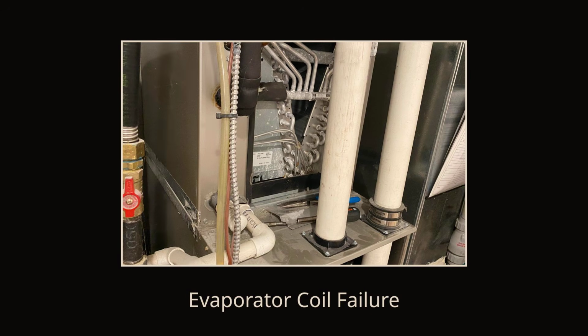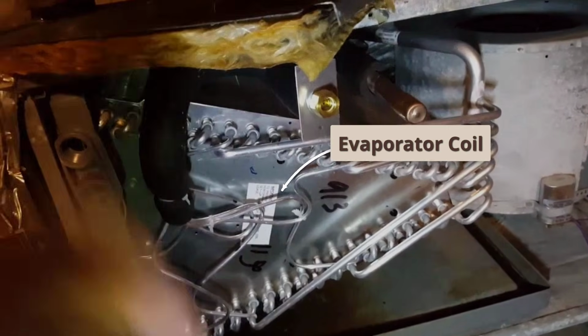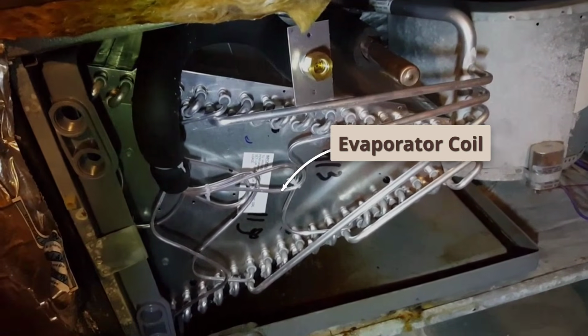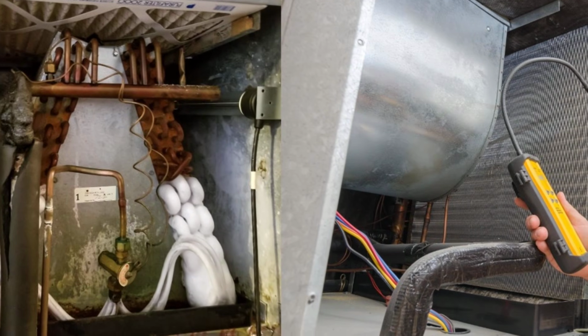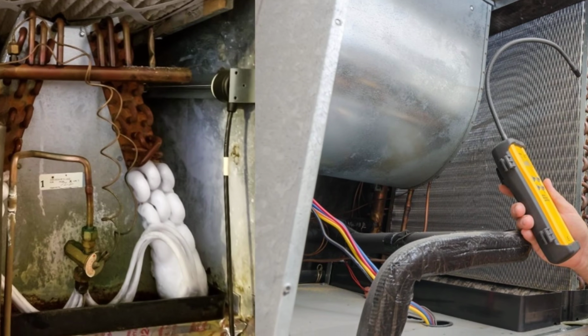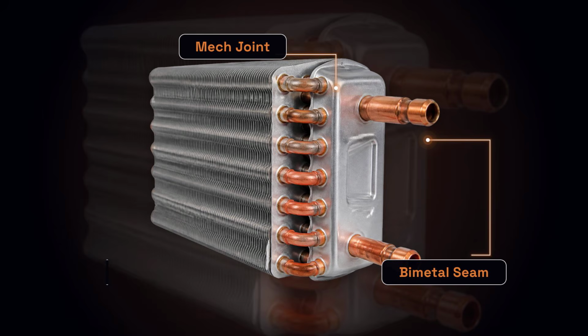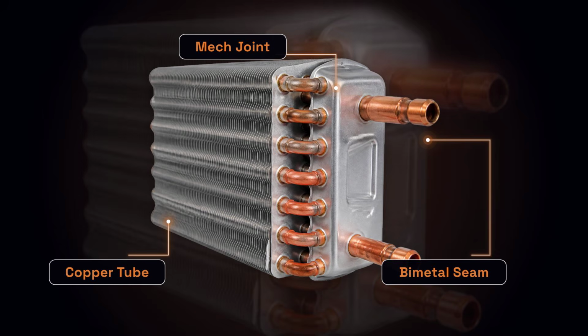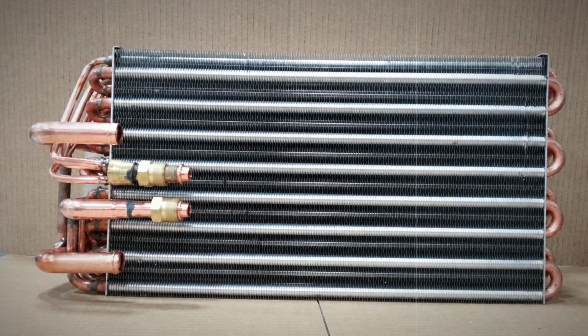In a central air system, the evaporator coil sits inside your home, usually mounted directly above your furnace or air handler, and it absorbs heat from your indoor air as refrigerant passes through it. Goodman built these coils using a bimetallic design. Copper refrigerant tubing mechanically joined to aluminum fins and headers.